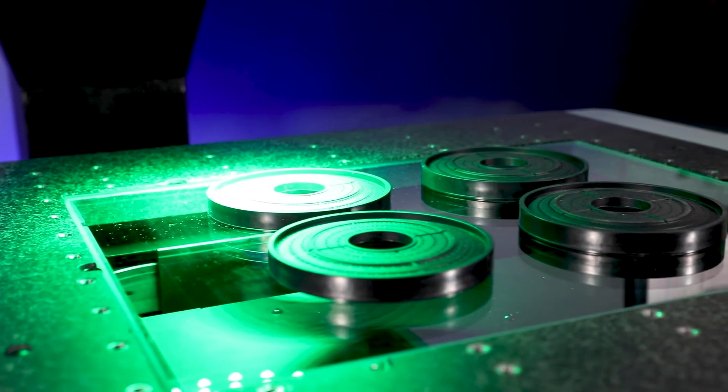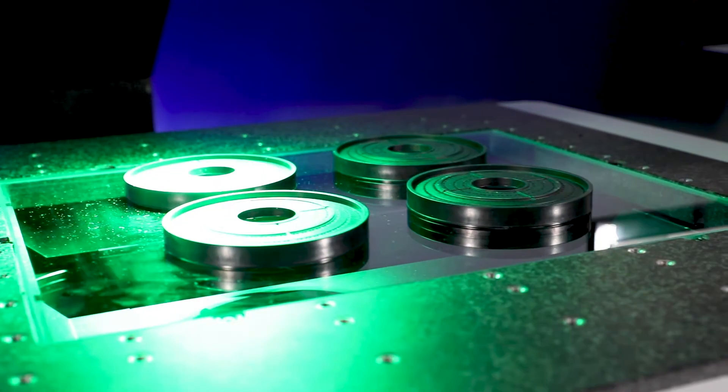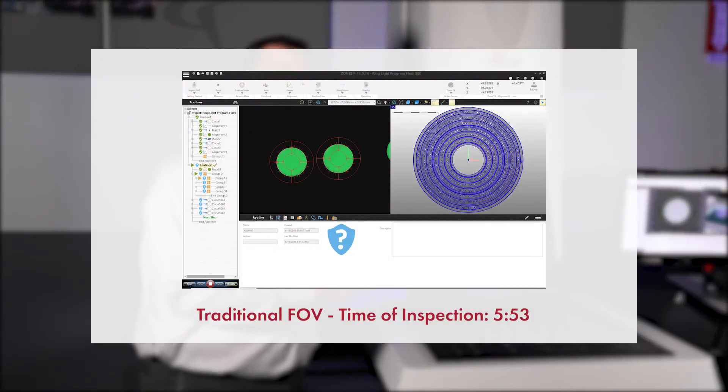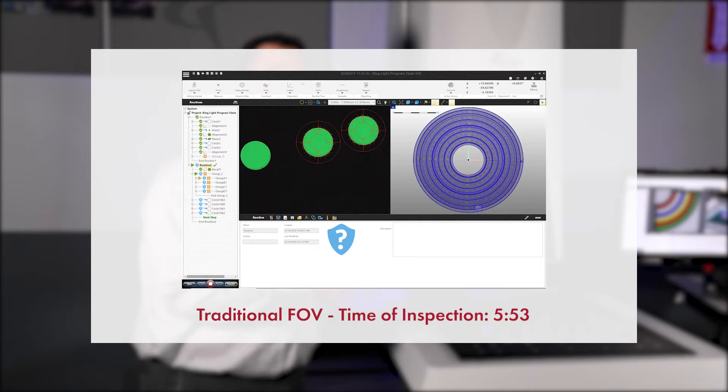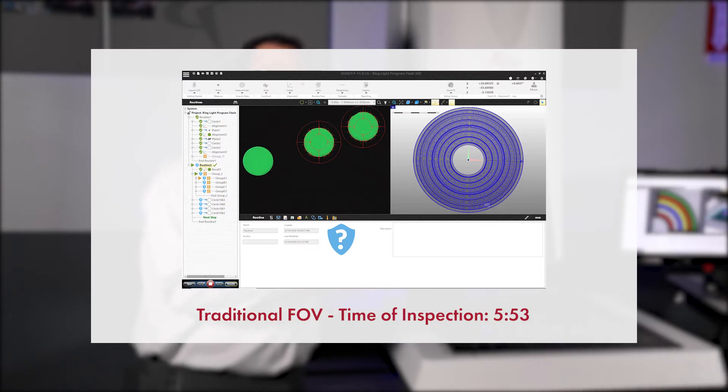These holes are at different Z-heights and different levels, but because of the large depth of field and the telecentricity of the Fusion optics, we're able to inspect all these holes in one snapshot.